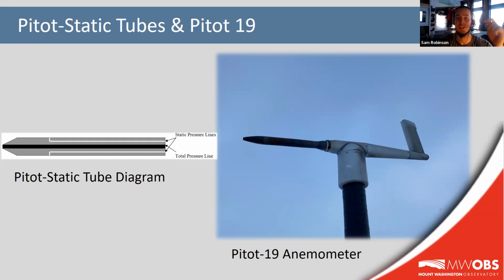So as air flows into that very end, the total pressure end, and also flows by the perpendicular static pressure holes, a difference in pressure is generated, which is called the differential pressure. This differential pressure can then be used to determine the velocity of the flowing fluid, which in our case is air. Its most common use nowadays is determining the airspeed of an aircraft.